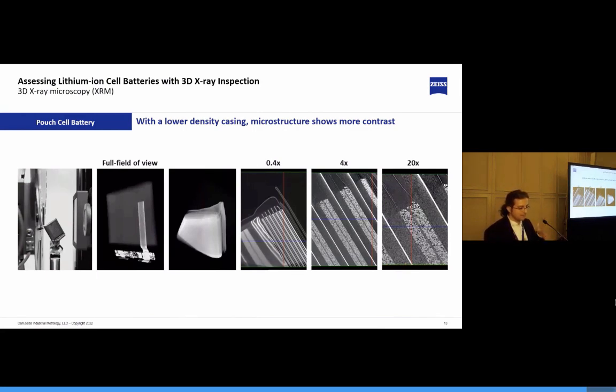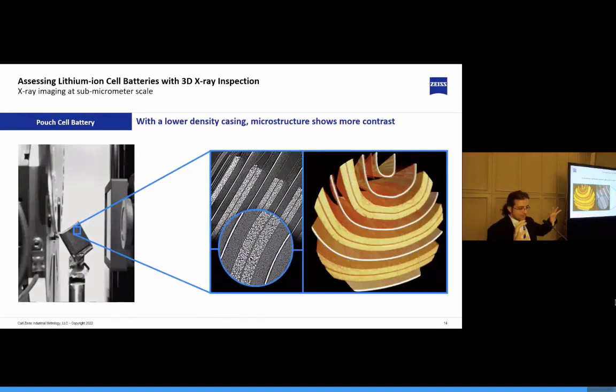In this example, you can see how, using different regions of interest, and in this case different lenses, the same battery can be scanned non-destructively to analyze different regions. You see images there with the full flat panel, and also with the small regions of interest with the 0.4x lens, the 4x lens, and the 20x lens magnification. So the resolution at a distance basically enables you to do this reconstruction. And remember, though you are seeing 2D images, those are cross-sectional images, virtual cross-sections from a 3D image. You get the full 3D information.